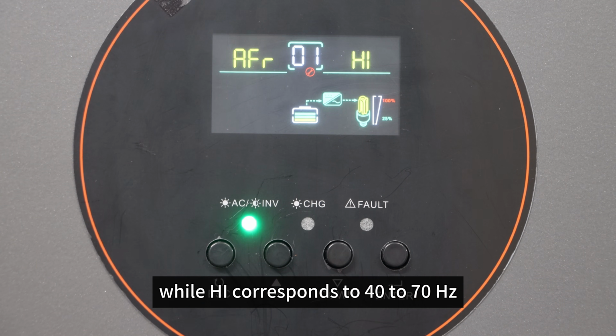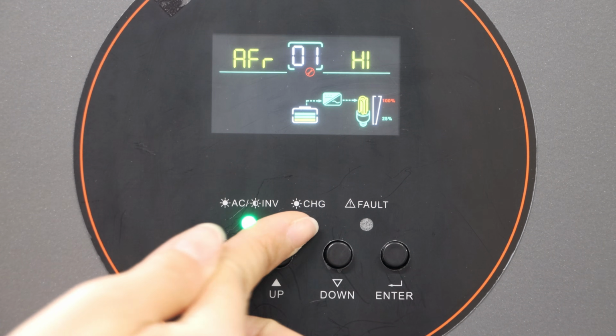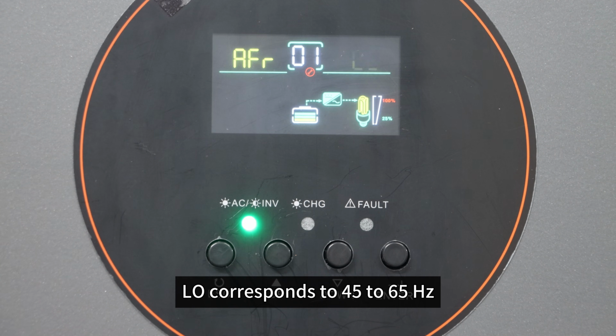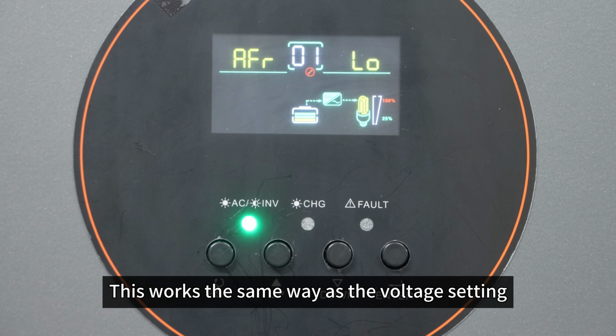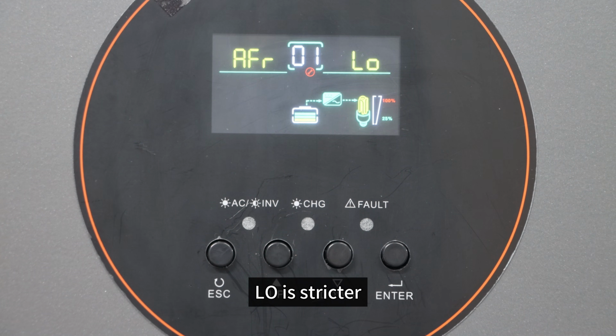HI corresponds to 40 to 70 Hz, while LO corresponds to 45 to 65 Hz. This works the same way as the voltage setting. LO is stricter and HI is more tolerant.